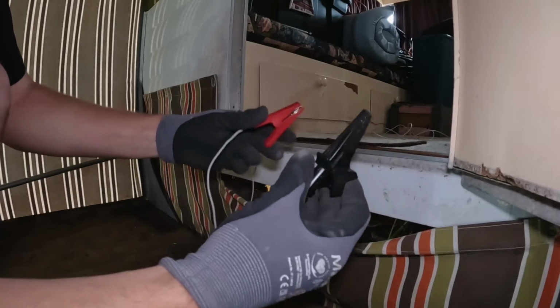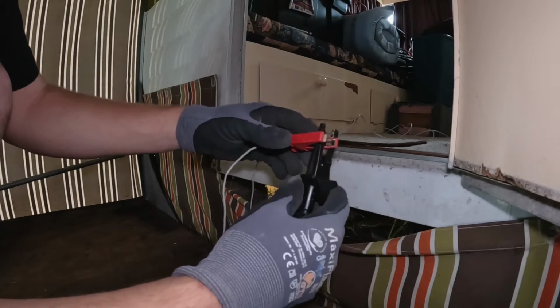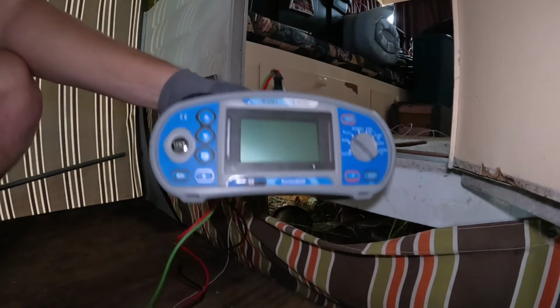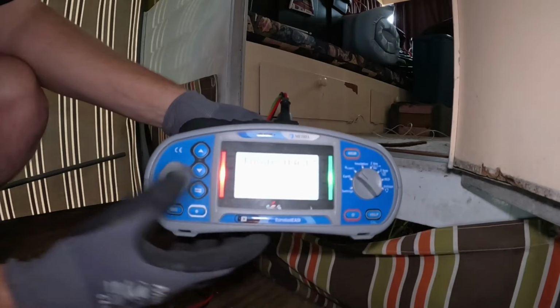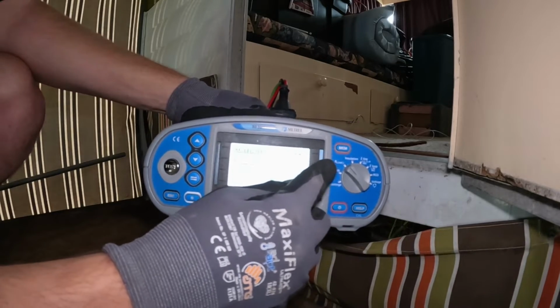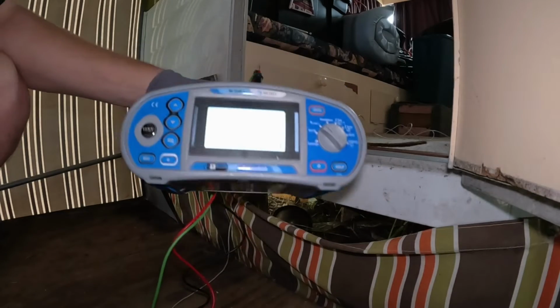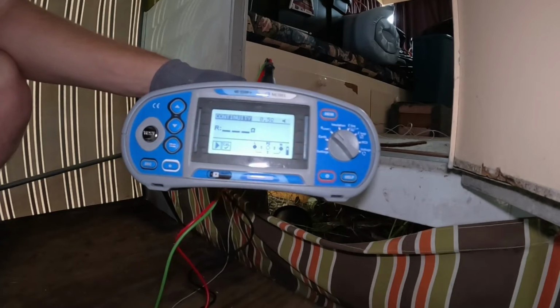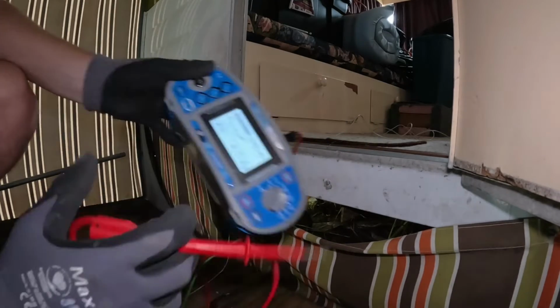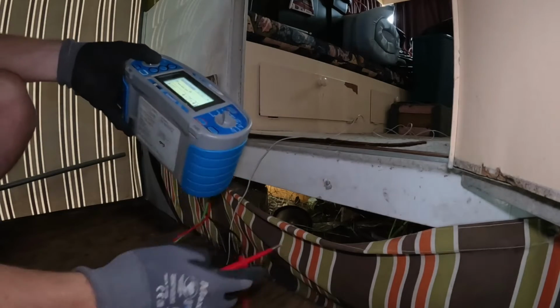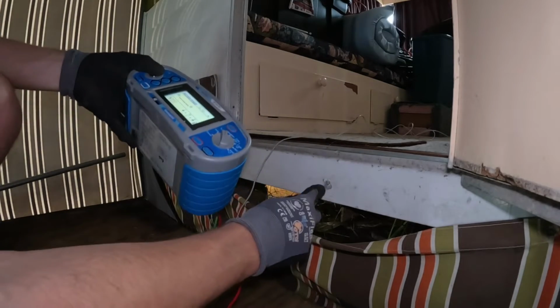Take the lead you've run out from the main switchboard, like so. Using your meter, turn it on and switch the setting to low ohms. It's always good to calibrate your lead first to make sure everything's okay. Then, using your test probe, attach it to any metal part on the body with a good clean connection.